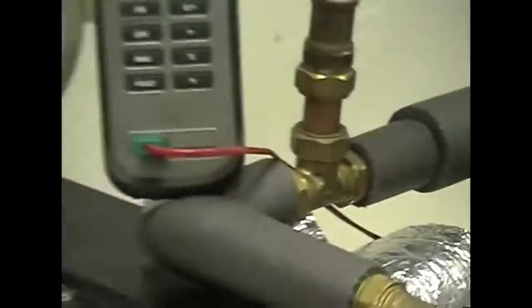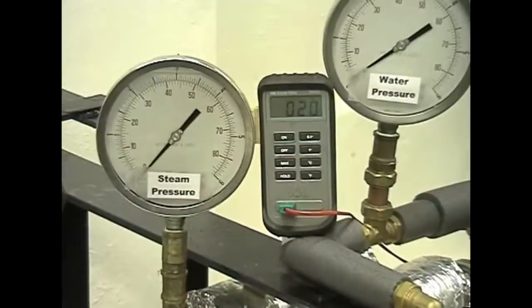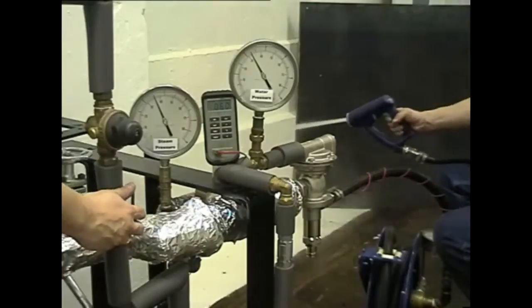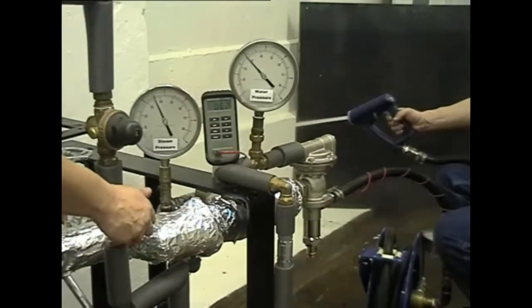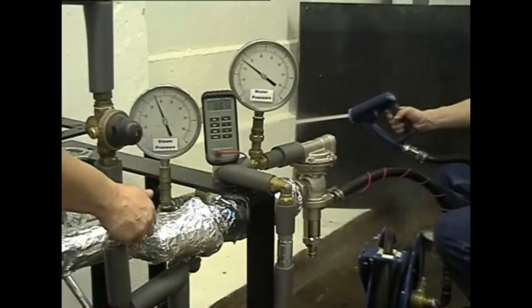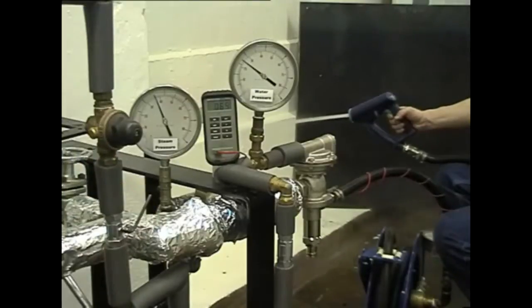The test starts with a steam pressure of 40 psi and full water pressure at approximately 33 psi. The SWM1 easily controls the water temperature to exactly 60 degrees C. If the water pressure is reduced incrementally to 25 psi...